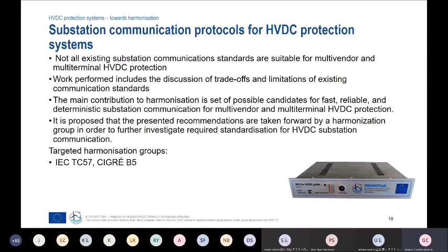Next, looking at the communication interfaces between the HVDC protection devices. When we're looking towards multi-vendor HVDC protection systems, we need interfaces between different protection components, for example protection IEDs, HVDC circuit breakers, but also between different IEDs and the converter stations. We need strong harmonization to define the functional requirements and specifications of these interfaces. The work presented is focused on the interfaces between the protection IEDs and between the protection IED and the circuit breaker.